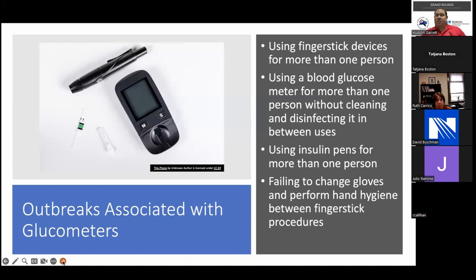It's important to go back to what was the intended use of those devices. Those were single patient use. That was how they were regulated. That's how they were sold. And they were only for commercial use in the consumer setting. They were never designed for hospital settings. They're actually labeled not for that. So it's important to think, even with basic stuff, we've still got risk.